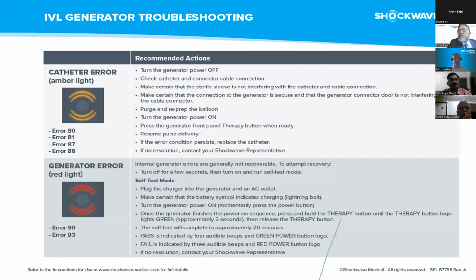This is generally always coming from the generator, and it is a generator error code, nothing to do with the catheter. Most of the time this is an internal fault with the generator that needs to be replaced. But there is a test we can do to confirm that before contacting anybody to replace the generator, and that's the self-test mode.